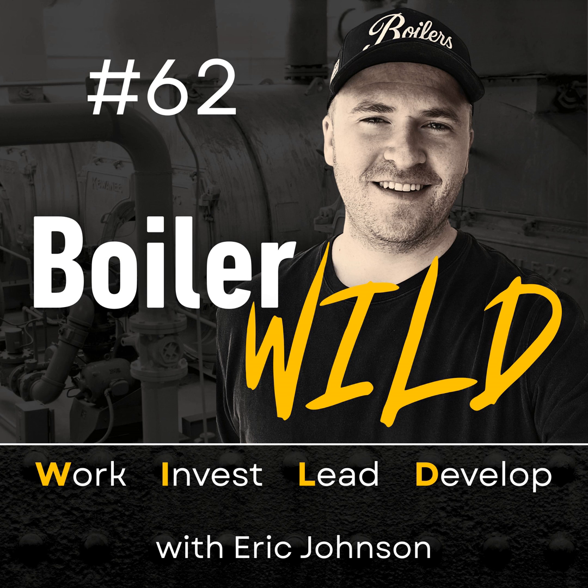You may want to look at the diffuser, pop an inspection plate open on the burner, and if there's some shiny spots on the diffuser or on the connections or whatever, you'll instantly know that somebody recently moved it. But you want to check it. That's a little bit more in depth on checking it. That is not where I would start. This list that we're going through is not in order, but there are higher level things I would start with. That is the air damper, that is the igniter, and the ignition transformer. They're more likely to cause an intermittent pilot issue versus a diffuser positioning that is slightly off, or the pilot tube, but it's possible.